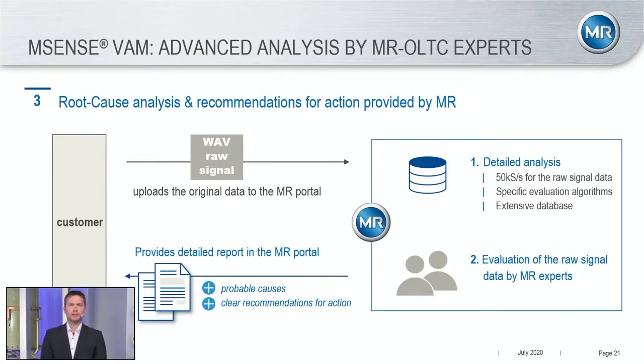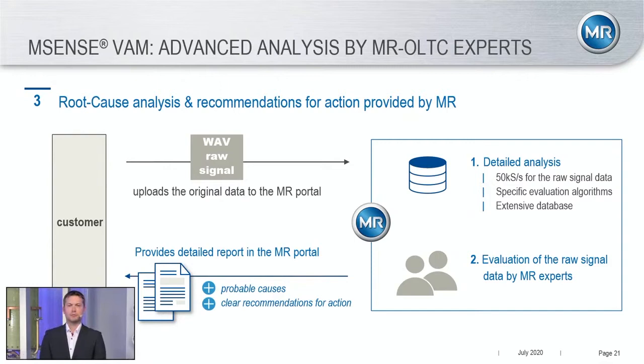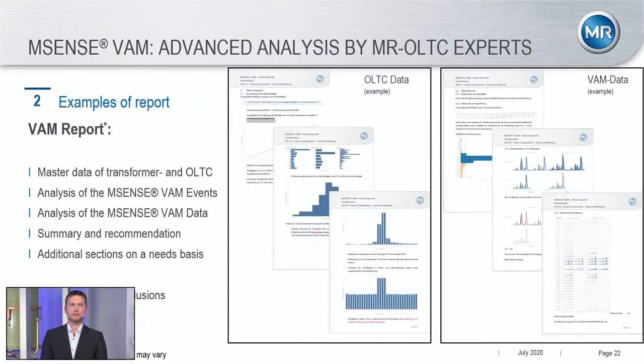The offline interpretation of the online data can be done either via direct access from our site to the device with a modem, or via a download of raw data sent to our database through the MR web portal. In the database, our experts can compare patterns over time, and if we have an original measurement pattern from our factory, they can compare the pattern over time with the very first one to indicate slow-moving failures. This of course cannot be done online — it needs to be done offline. The result of this interpretation will be a report with clear recommendations for you as the operator of the tap changer and transformer.